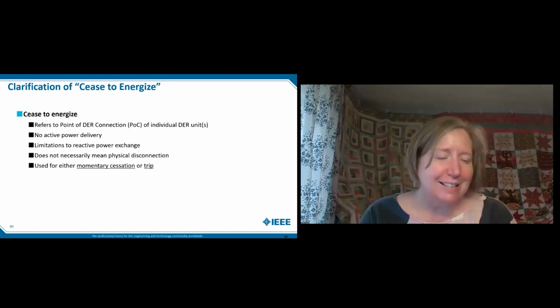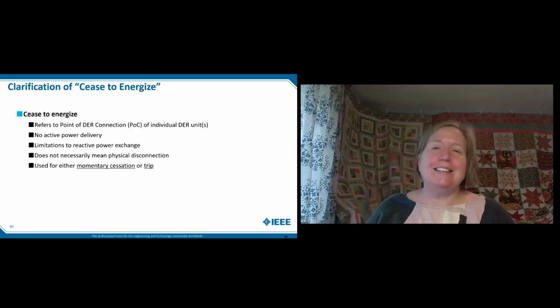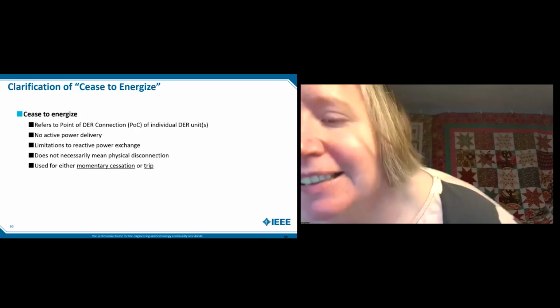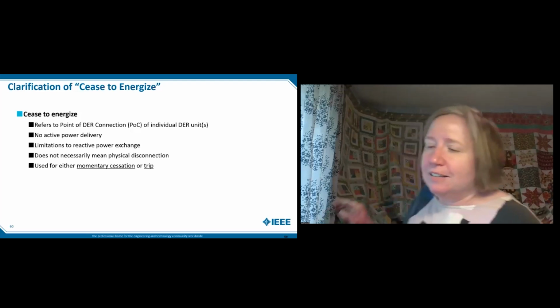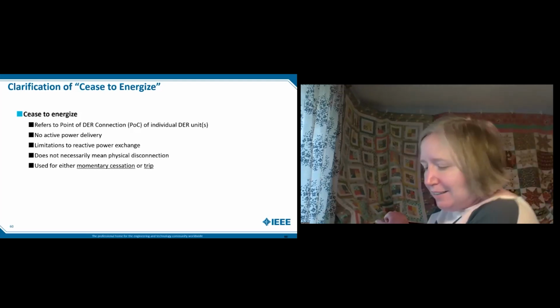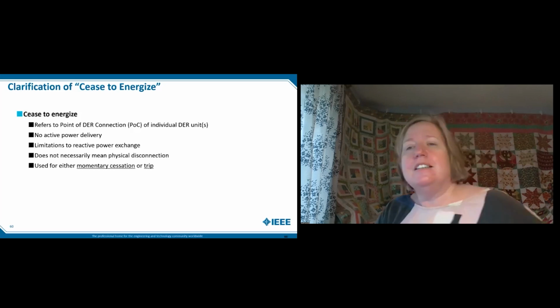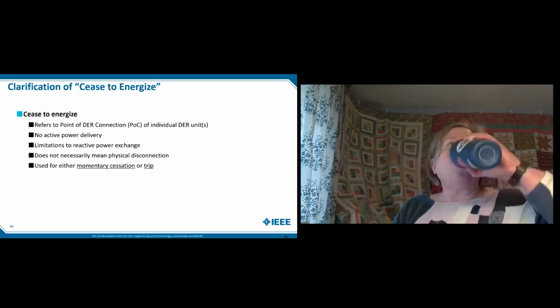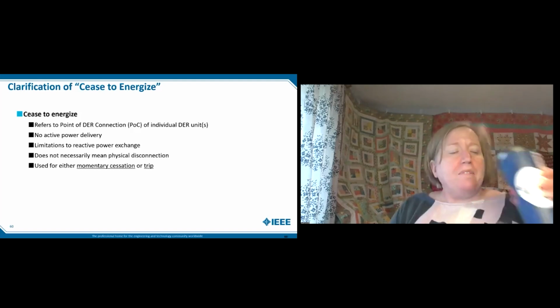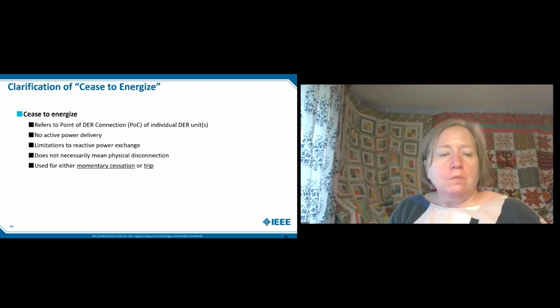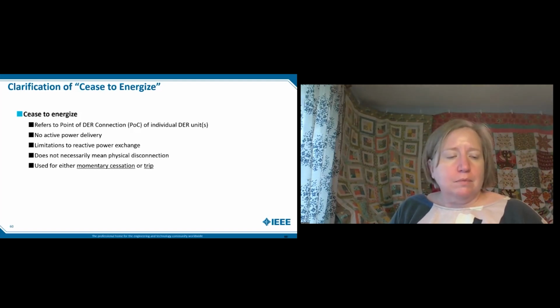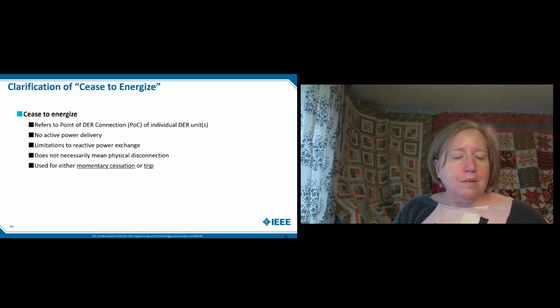Yeah, that's an important point. When you have all this reverse flow because there's no load and all the PV is on, you could outright reach the ampacity limit of the circuitry or components. I've seen that. Another problem I've seen is on some systems, you'll get a bunch of single phase systems and you could trigger imbalance such that if you have a 4-wire system, your neutral return will hit its limit. I've seen that happen, so phase balance becomes an issue. Now, to jump ahead, there are advanced 3-phase energy storage systems that could do interphase balancing and lift these limits.